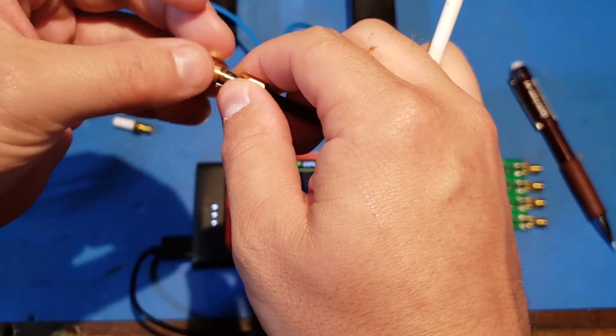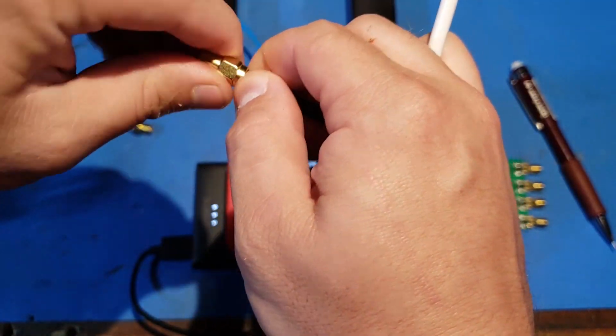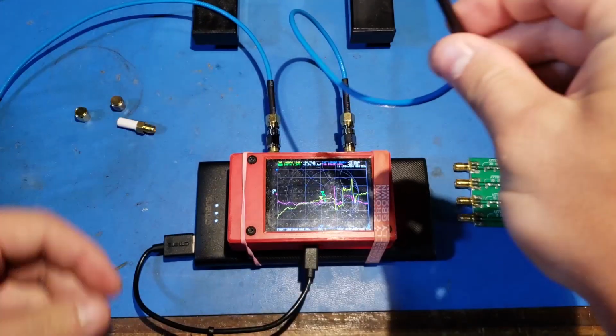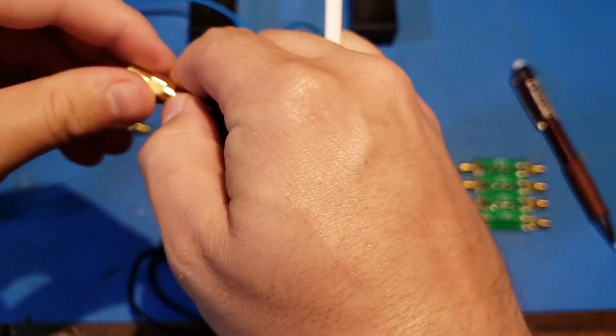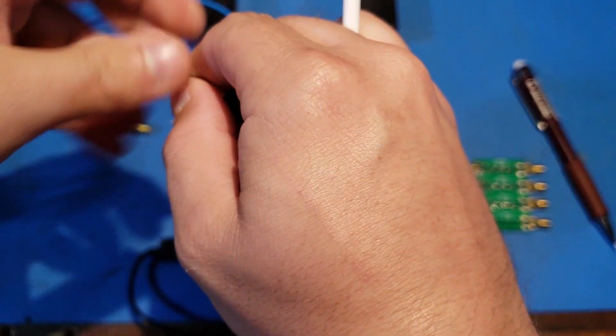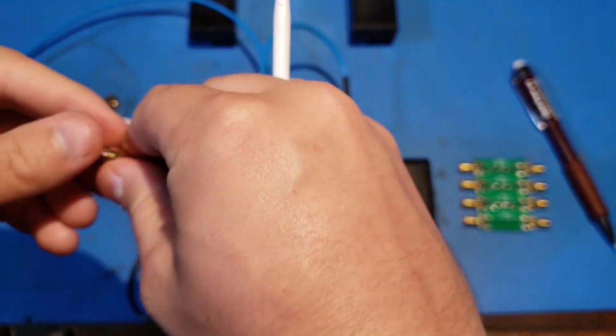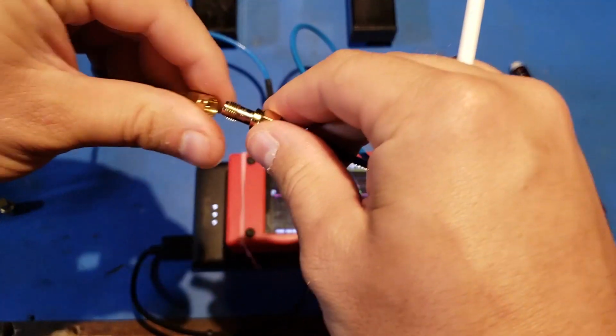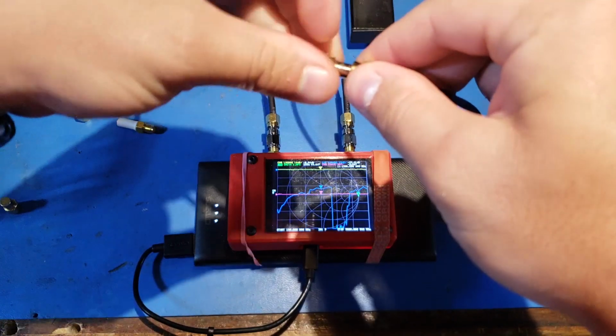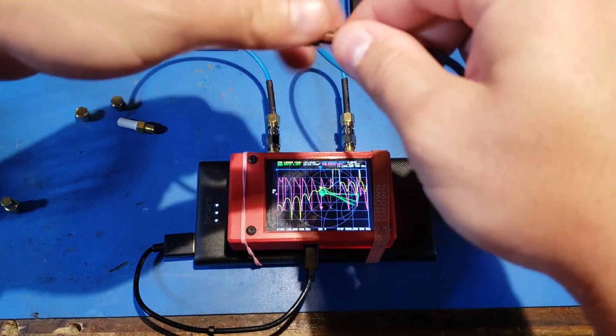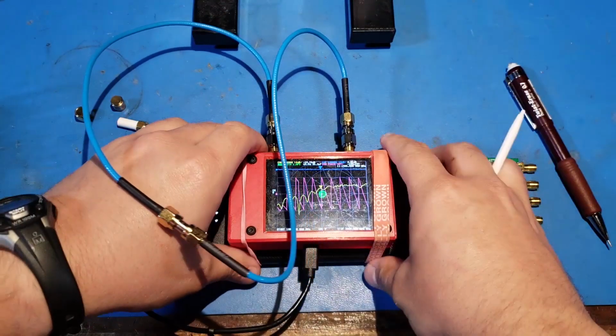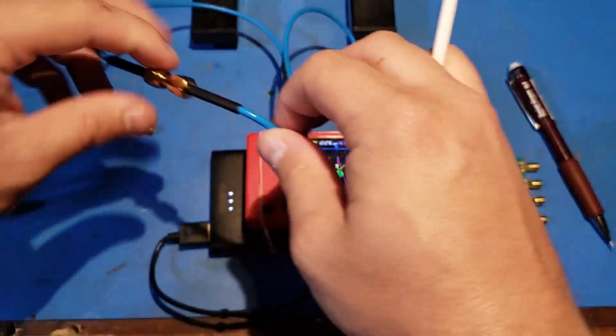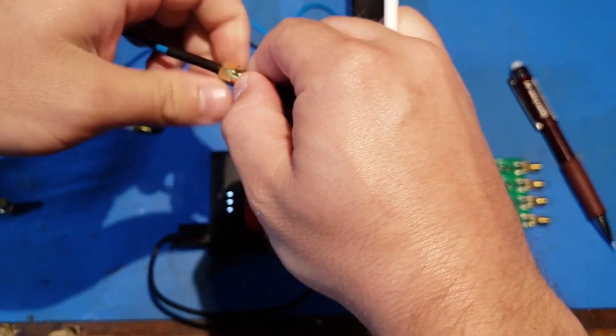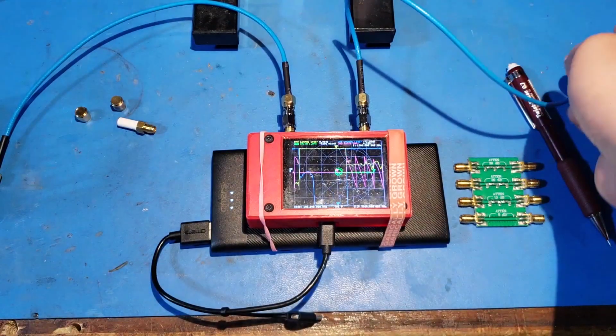Okay. We see a dot in the center of the Smith chart, so it looks like that's good. And we'll check our through measurement on this one because this was indeed a 2-port calibration. So this should look similar to 50 ohms, and our through measurement should read no attenuation here. 0.01 dB, cool, and it's pretty darn close to a match to 50 ohms there. So I'd say calibration 0, good to go.